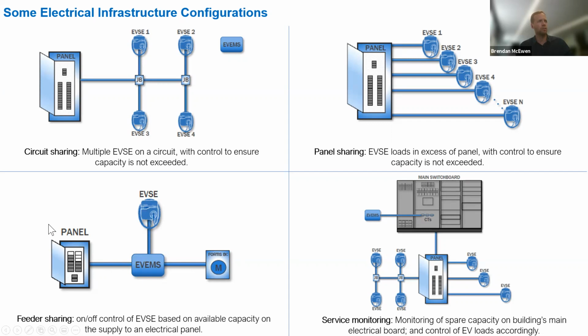There are other ways you could do this, like load switching - having the EVSE off of a branch circuit off the panel, or having the EVSE and, say, a dryer share the same circuit or power allocation. So either your EV charging can be occurring or your dryer can be on, but not both, which avoids overloading your panel. That's perfectly fine, because usually we don't have our dryers running all through the night, so there's plenty of hours for the EVs to charge.